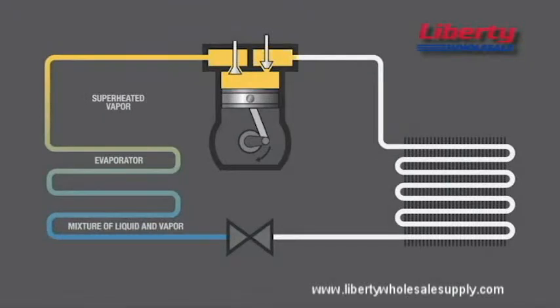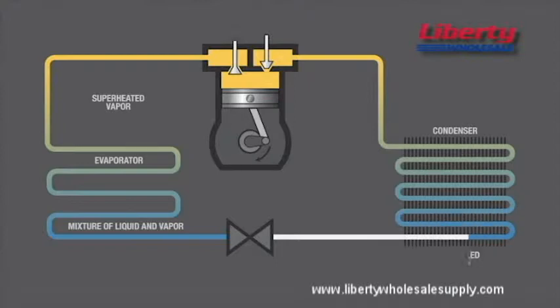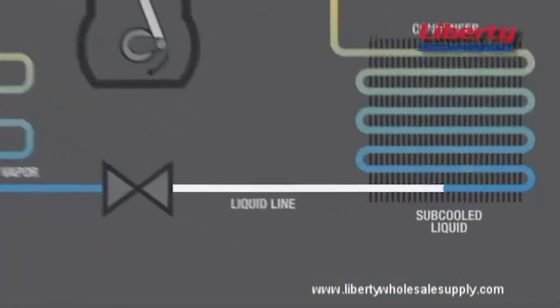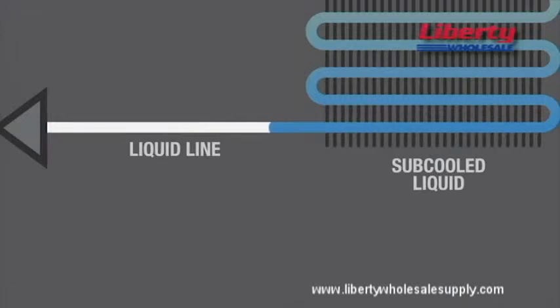Now let's look at subcooling. As refrigerant enters the system's condenser, it's in a vapor state. As heat is removed from the vapor, it will turn to liquid at its saturation condensing temperature. After the vapor has turned to liquid, any temperature of the liquid below this saturation condensing temperature is called subcooling. Because the efficiency of the system is optimized with subcooling, you want to make sure that you have a constant supply of liquid to the evaporator. It's important that the refrigerant is subcooled to prevent it from turning to gas before it gets there. A smaller amount of refrigerant is required to maintain the desired temperature, which means less work for the compressor.